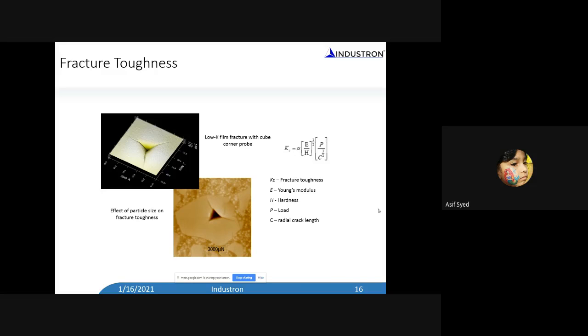Again, because we have the imaging capability, you can indent a ceramic material. When you indent a ceramic material with what we call a corner cube indenter tip, which has a higher strain, you generate cracks, and you can measure the crack length through the image. And you know the Young's modulus and the hardness from the same indentation experiment. With all these parameters, you can even calculate the fracture toughness. It's not as quantitative as a regular fracture toughness measurement, but for ceramic material, if the crack length is much longer than the width of the indent, it does work. So in that process, you can calculate the fracture toughness of this material.